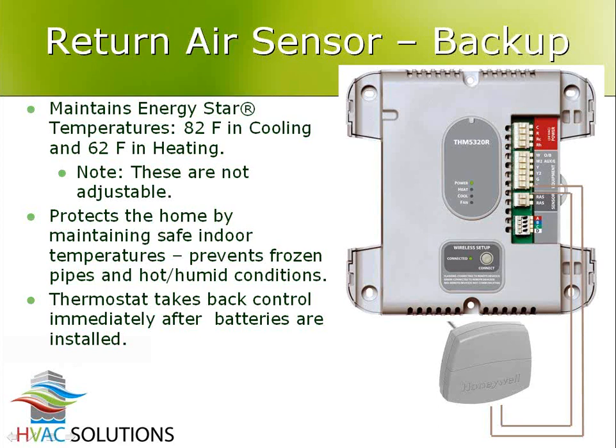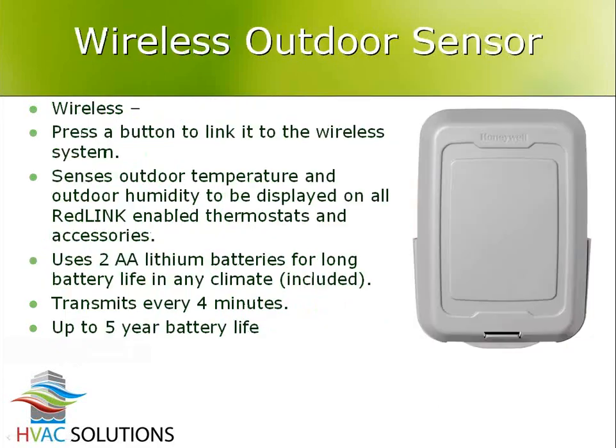And then on the cooling side of the equation, the reason we plug 82 in is the same thing. We want it to be warm enough that you're uncomfortable and you have to go figure out why you didn't change your batteries. But we don't want it to get totally out of control and have humidity become a concern and mold and all that stuff. So we maintain the Energy Star temperatures of 82 and 62 to prevent freezing and over humidity conditions. Once you put batteries back in the stat, in a couple minutes they start talking to the equipment again. Life is good, and return air sensor goes back to being just a fail-safe.